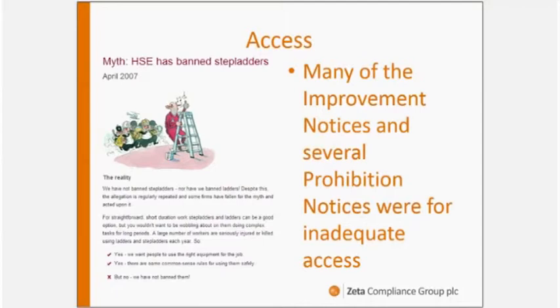concerned with inadequate access. Now, I had assumed that if you serve a prohibition notice, my understanding of it was that it prohibited a practice. For example, an unguarded machine: switch off that machine until it is guarded. And I would have thought a prohibition notice for access to a cooling tower would prohibit the activity of gaining access. So you can't get to look, for example, at the drift eliminators. Don't go up there. But no. If you can't safely inspect the drift eliminators, the prohibition notice can apply and stop you running your cooling tower.